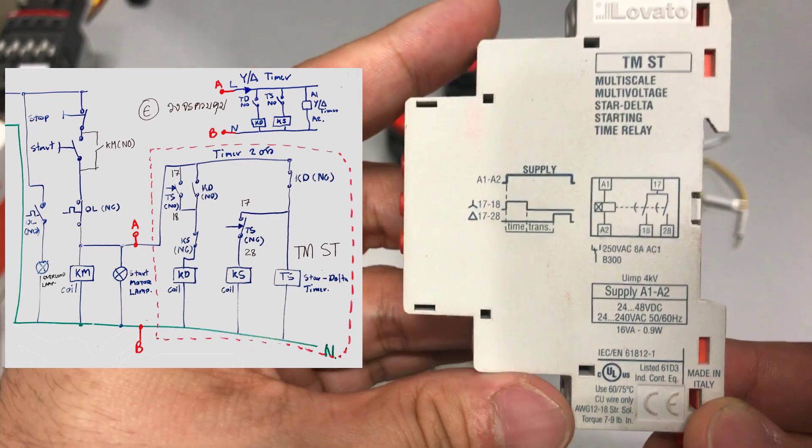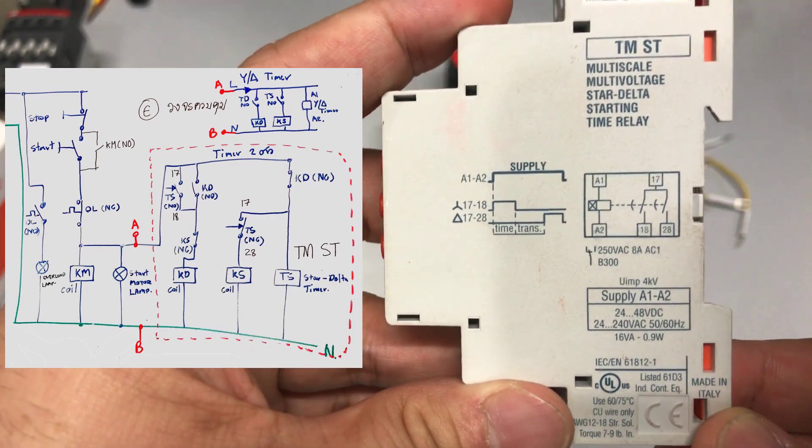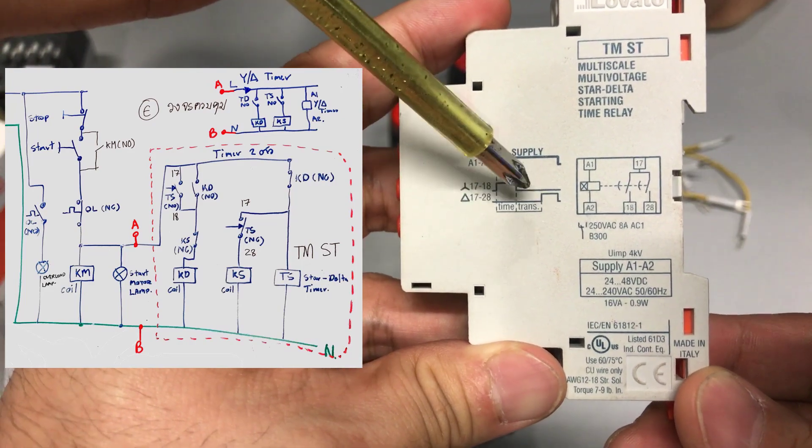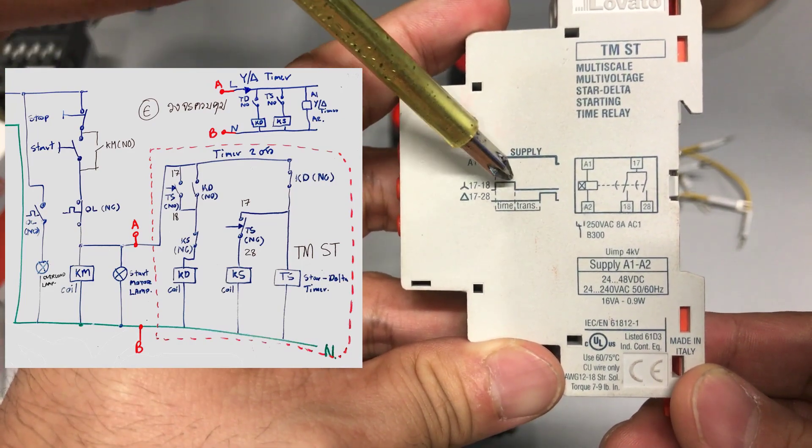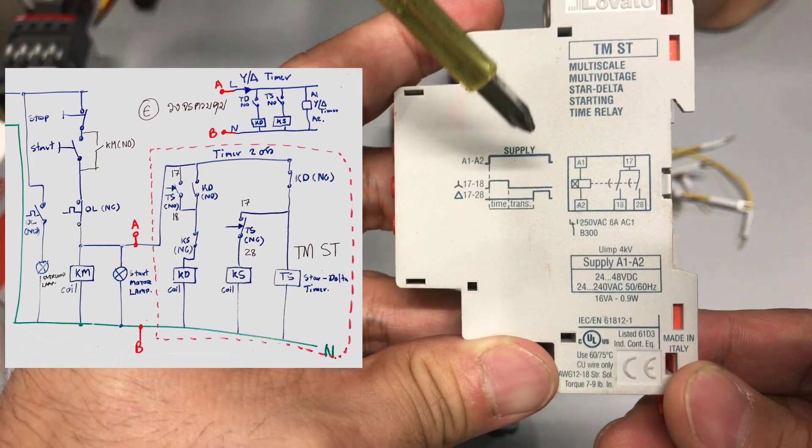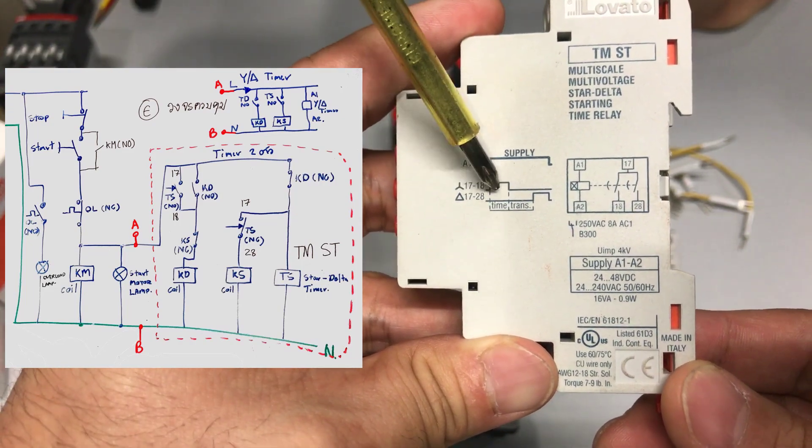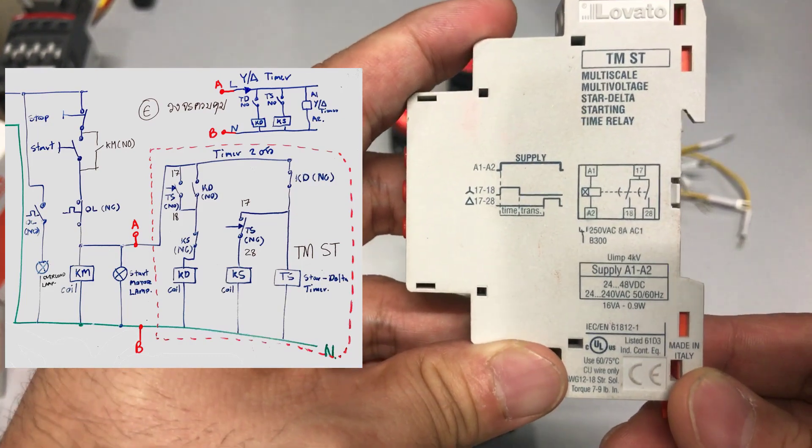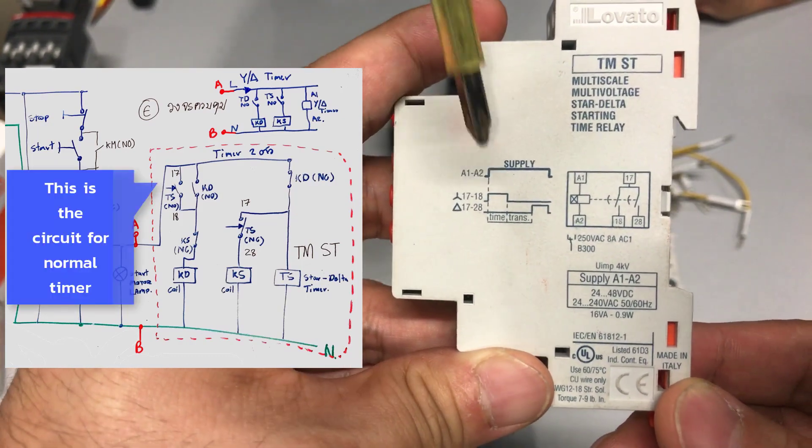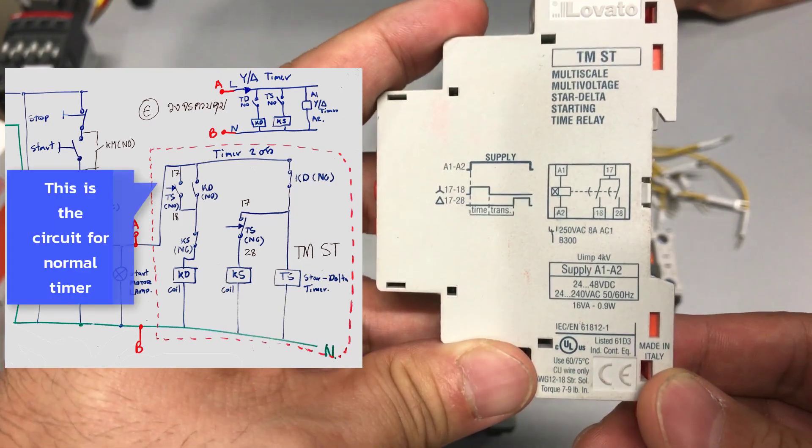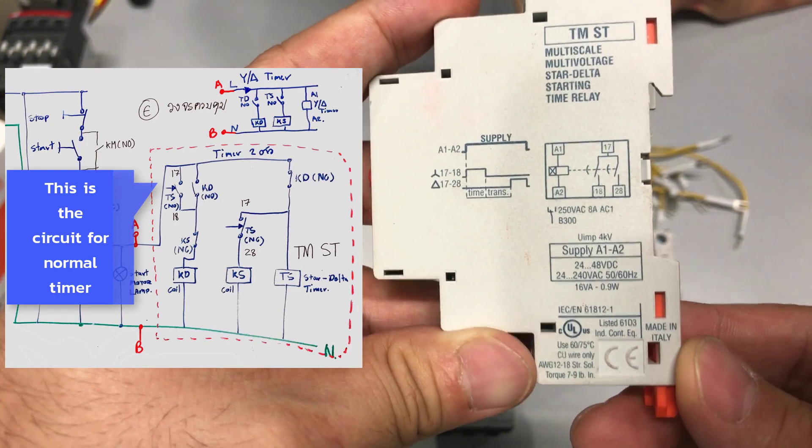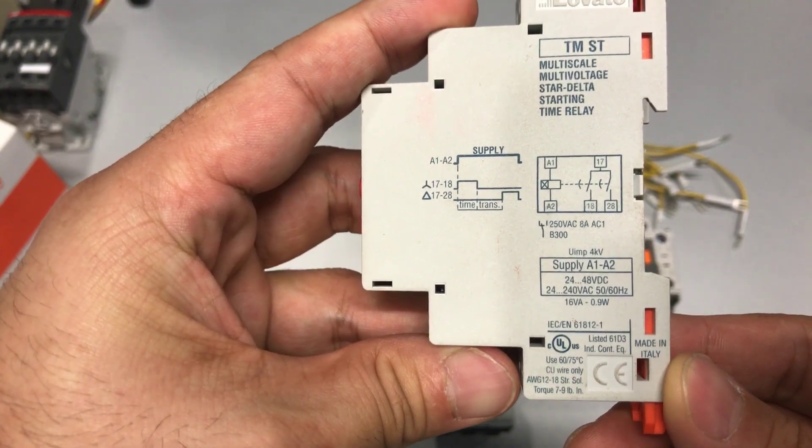Now, if you were to use a normal timer, there will be no transition delay. The timer will immediately switch the contactor from star to delta. This will work okay, but there's a chance that both star and delta contactors will be working at the same time, and this may cause some problems. In the diagram, we show both the circuit for the normal timer and the star delta timer.